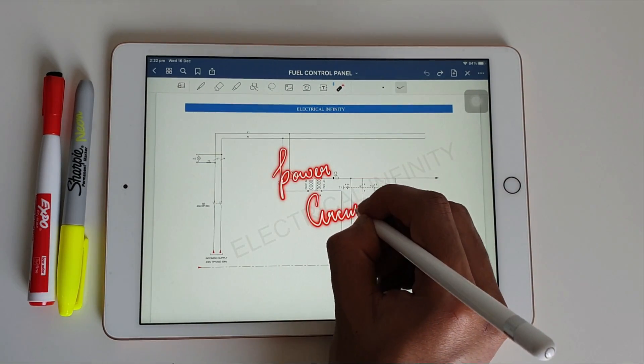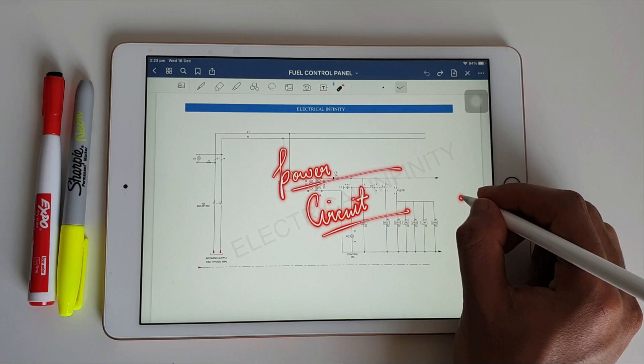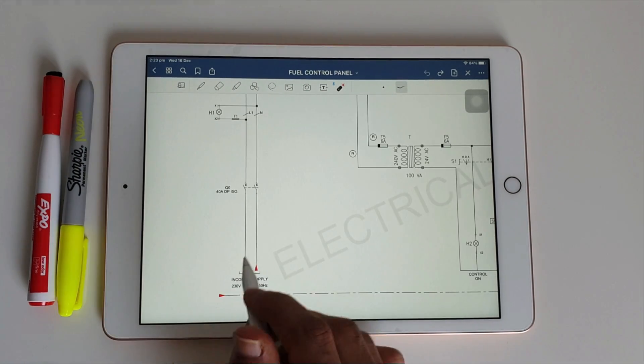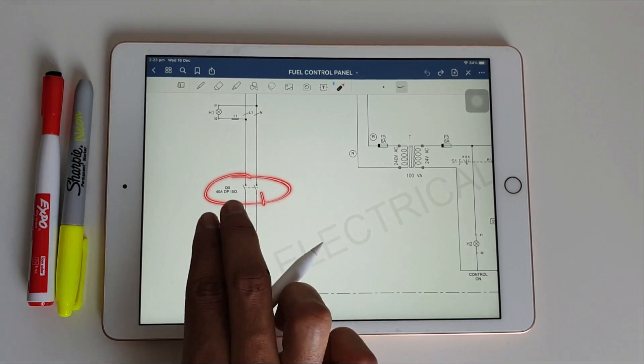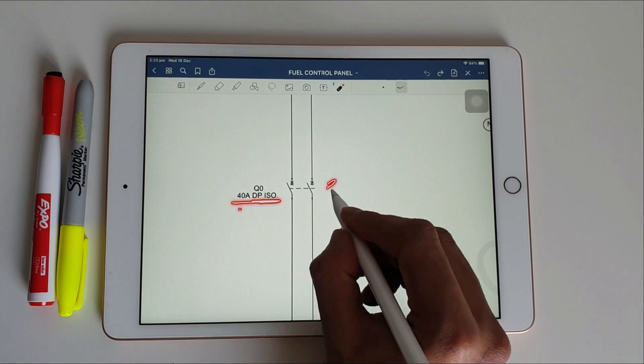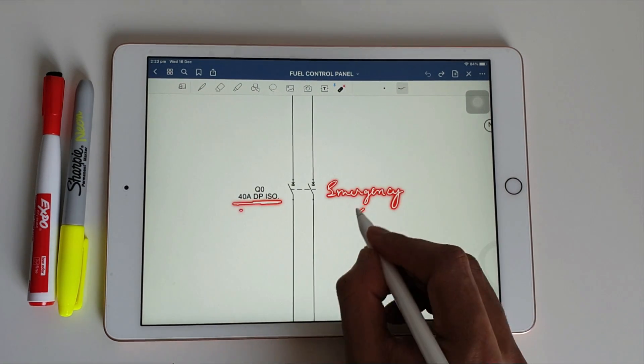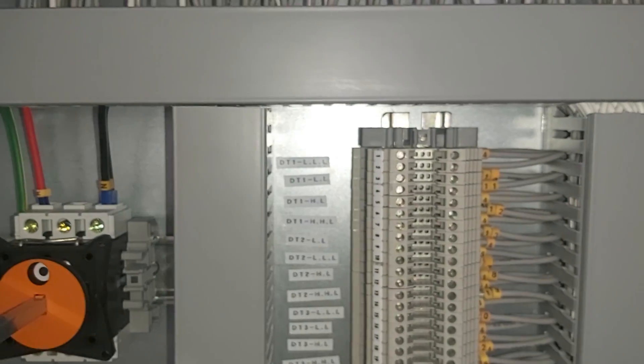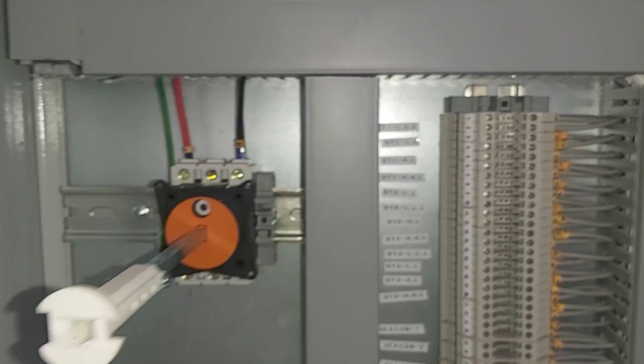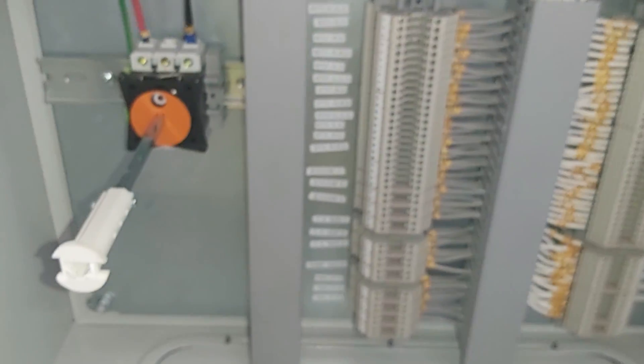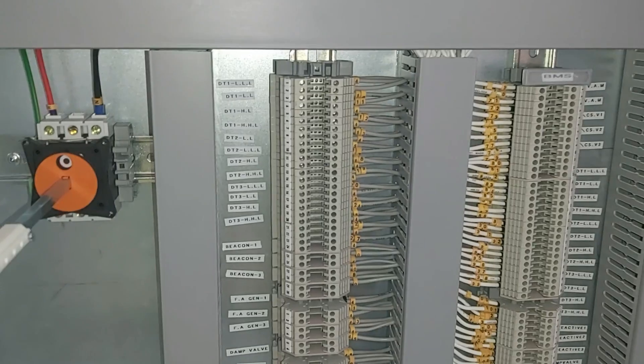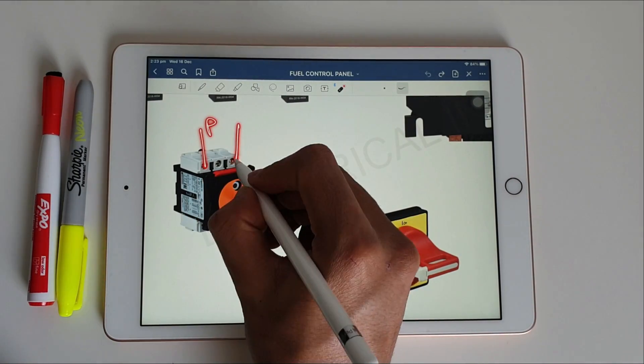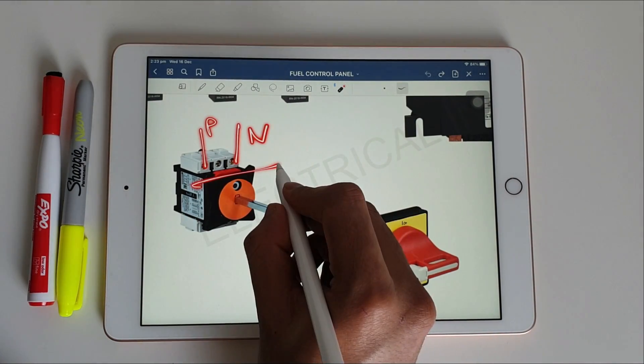First I'm going to explain the power circuit of this panel, and later I will explain the control circuit too. In the power circuit we have an incoming supply of 230 volts, single phase, 50 Hz. We are using a 40 ampere double pole emergency switch by Schneider, which is used for turning the complete panel on and off. It has three terminals but we are using two — one for phase and one for neutral.